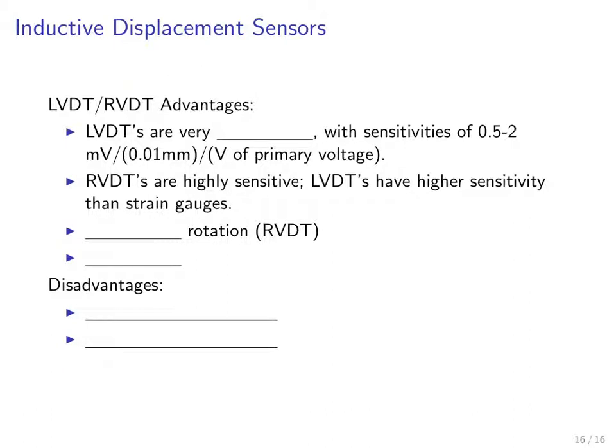We'll finish up with advantages and disadvantages. One advantage of LVDTs is that they are very linear, with sensitivities of about 0.5 to 2 millivolts per 0.01 millimeters of motion per volt of primary voltage. The output voltage is linearly proportional to the primary voltage. RVDTs are highly sensitive, and LVDTs have significantly higher sensitivity than strain gauges. The RVDT allows you to do infinite rotations. You can keep spinning the shaft and getting a readout continuously. They are very rugged devices.